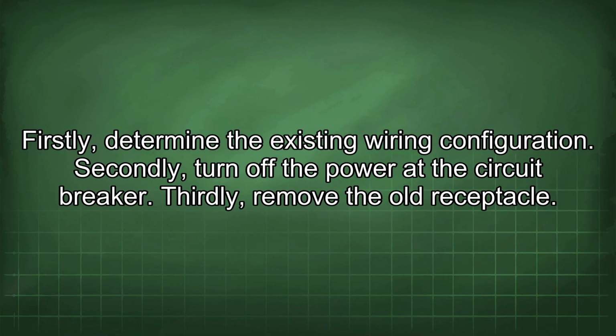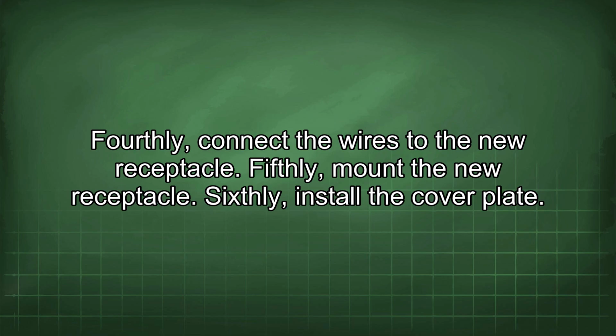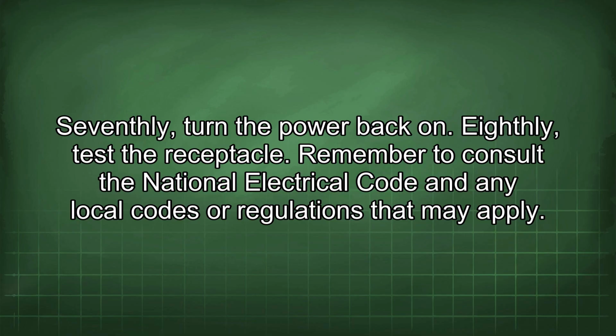Firstly, determine the existing wiring configuration. Secondly, turn off the power at the circuit breaker. Thirdly, remove the old receptacle. Fourthly, connect the wires to the new receptacle. Fifthly, mount the new receptacle. Sixthly, install the cover plate. Seventhly, turn the power back on. Eighthly, test the receptacle. Remember to consult the National Electrical Code and any local codes or regulations that may apply.